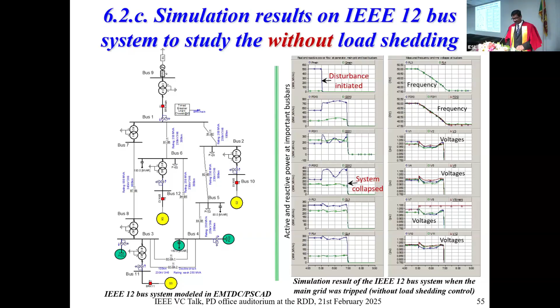So you have load shedding. CEB has load shedding techniques: under-frequency load shedding and under-voltage load shedding. But the technique itself is a little old, working with a response range of a few seconds. Newer technology responds within 20 milliseconds, a fraction of a second. We have to upgrade the load shedding technique so the action is taken immediately. The breaker will still take some time to open mechanically, but the brain will take the decision instantly, unless we have another breaker system.